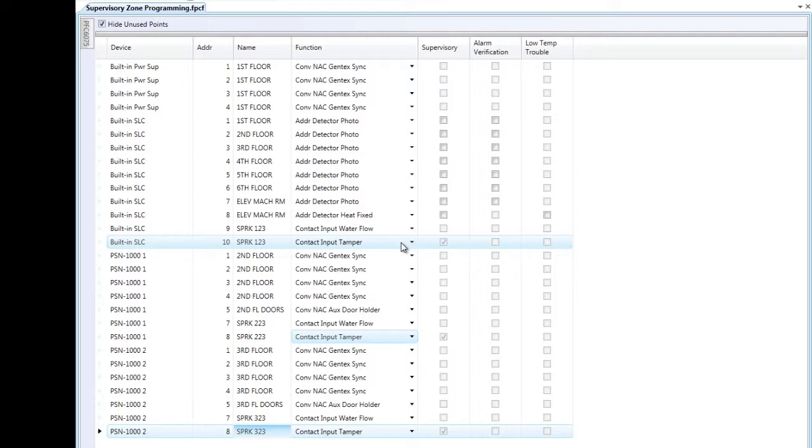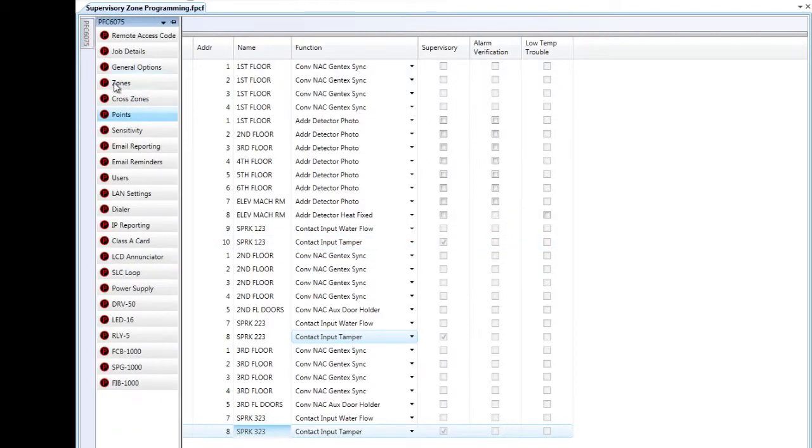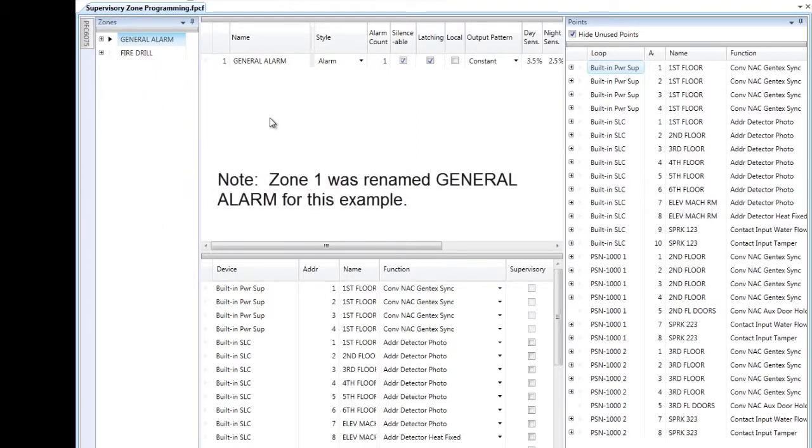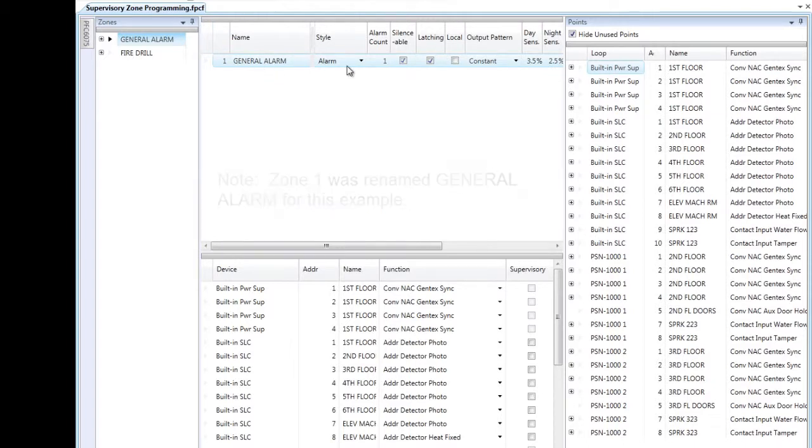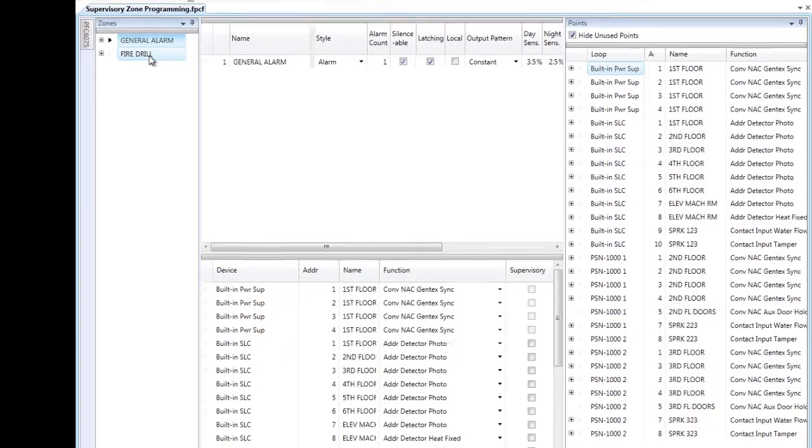Now when you do the learn at the fire alarm control panel, it's going to assign everything that it finds into zone 1. So currently, all of my points are in my general alarm zone that I've created here, and it is an alarm style zone. I've also gone ahead and created a fire drill zone, which has all of the outputs that I wish to activate when the fire drill button on the front of the fire alarm control panel is pressed.